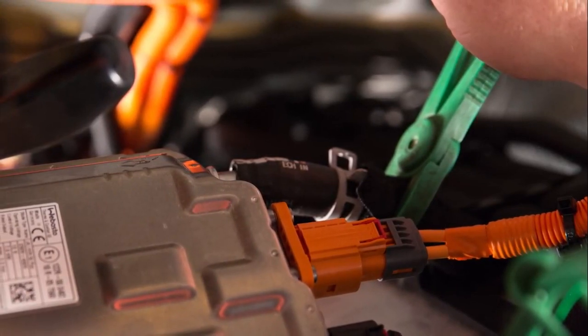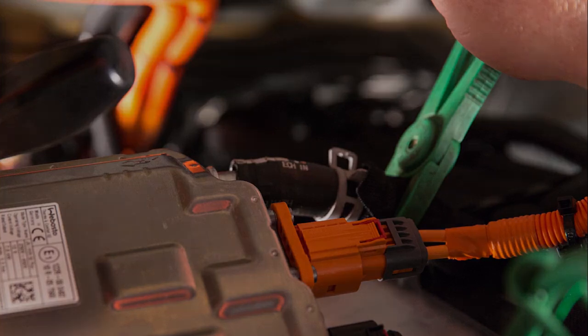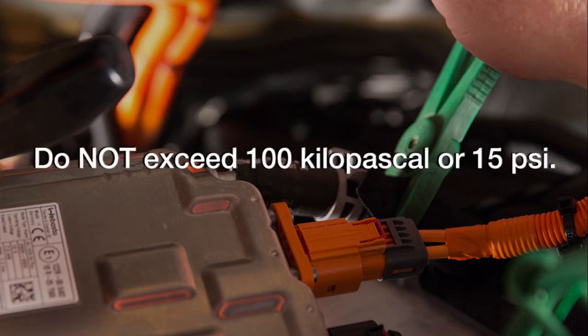If all coolant must be removed, as in the case of an ECH replacement, force the coolant from the ECH outlet port by applying shop air to the inlet port. Do not exceed 100 kilopascal or 15 psi.